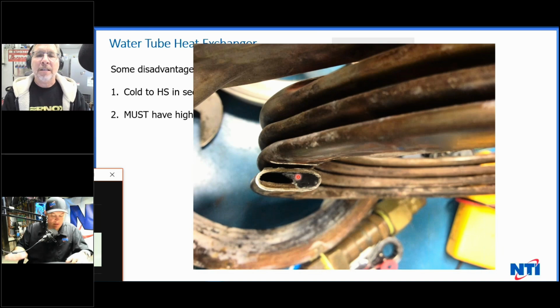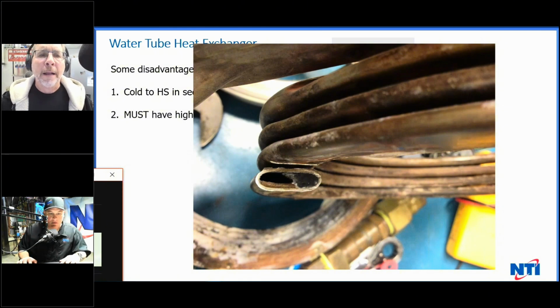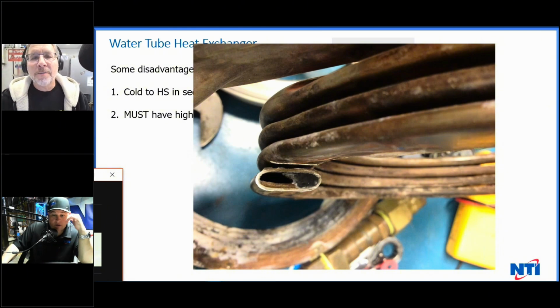And he made this statement. "Well, would it have made a difference? The last 3 years I had a 007 on as the boiler pump, and I just put the recommended 0011 on. Would that have made a difference?" No, we write installation operation manuals and put in the circulator sizes for no good reason at all. Of course it would. So yeah, it would have made a difference.